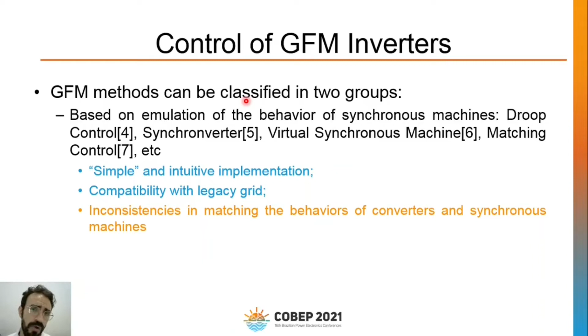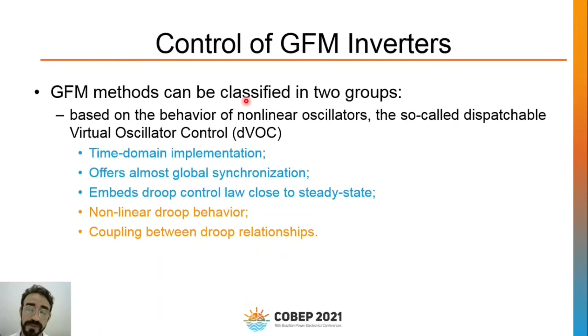The second group is the group of controls based on virtual oscillator control, which emulates the behavior of nonlinear oscillators. They have time domain implementation, which makes them faster when compared to control methods based on quasi-steady-state behavior. A very interesting point about these controls is their almost global synchronization, which comes from the theory of synchronization of networks of coupled nonlinear oscillators. And also they embed a droop control law close to steady state, which is mandatory for the compatibility with legacy grids. But they have nonlinear droop behavior, which is not clear if it's the optimal behavior for sharing power. And also they present coupling between active and reactive droop relationships.